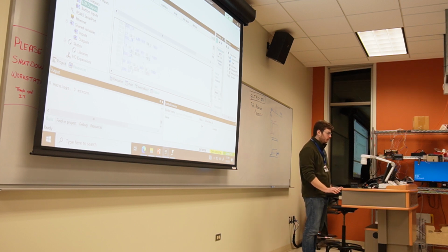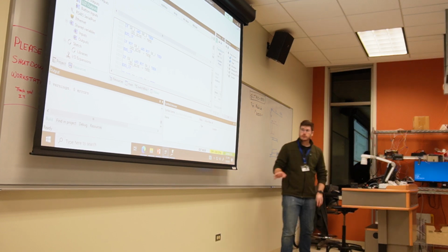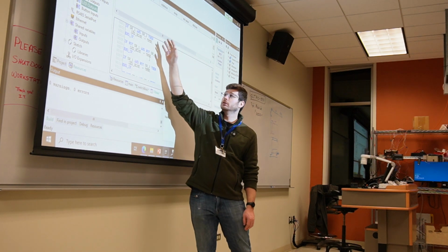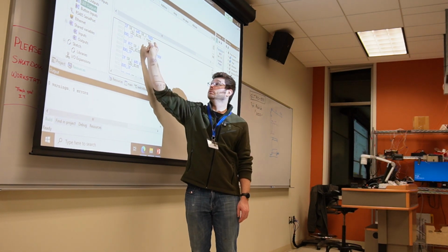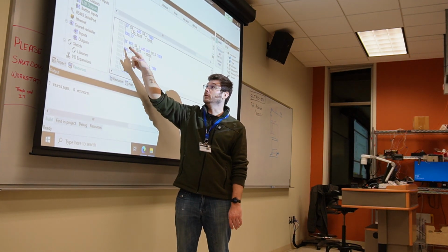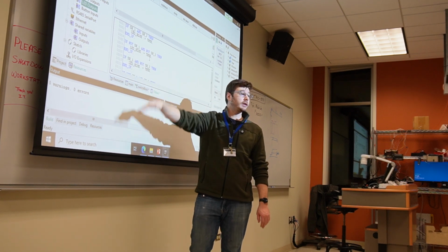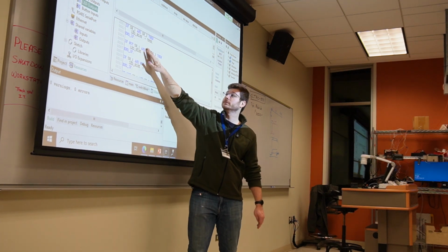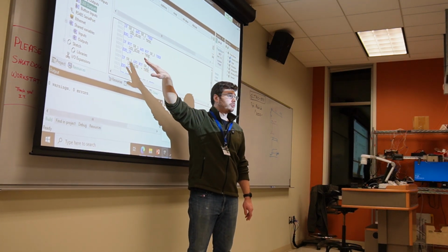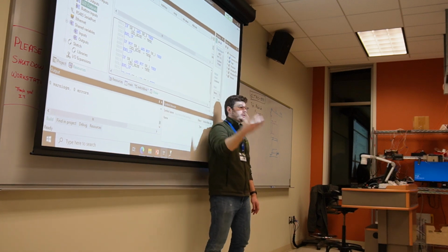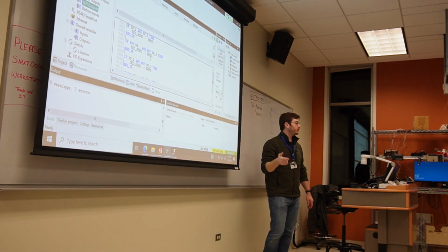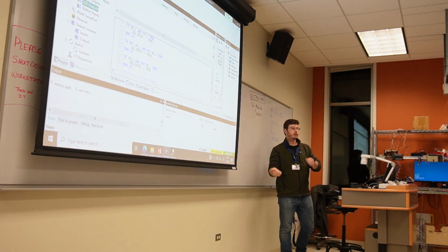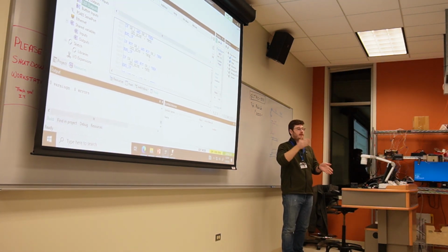The way that the PLC would run is it would evaluate all of this code. It would run line 1, then line 2, then line 3, and then 5, 6, 7, all the way down. Then it would see what the outputs are. What is the final state that LED blue is set to, true or false? Then it'll update that output accordingly. You guys remember the PLC scan cycle? We see our inputs, we run our code, and then we write our outputs. That happens in that order.